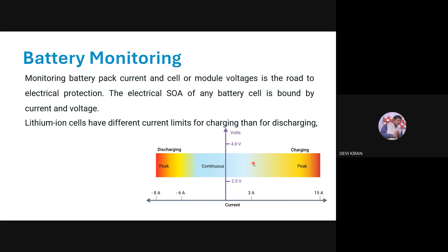Peak charging and discharging mostly occurs when connecting to an almost dead battery, maybe with 10% of charge left. You cannot expect this peak charging or discharging to be performed at 90% or 95% state of charge. If 90% of the battery is already charged and you expect it to go to 15 amps, it won't support that, and if it does, the battery or cell might get damaged. This is one example I'm showing for battery monitoring, I hope it is clear.